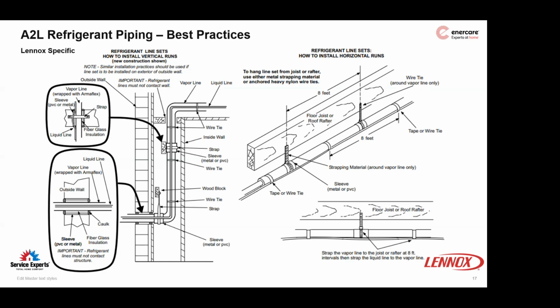The one thing I really like about the way this is drawn up is right here, they even suggest isolating the line set in your penetration through the exterior, with either a bead of silicone or some sort of sleeve. When I ran the line set in my house last year, I put it through a sleeve, like a piece of ABS, so that it didn't communicate directly with the building, and then filled the sleeve with silicone. It actually made for a nicer joint.